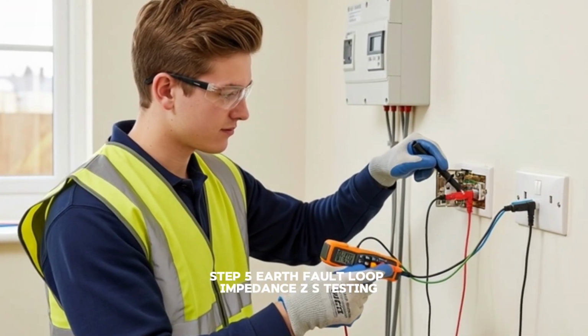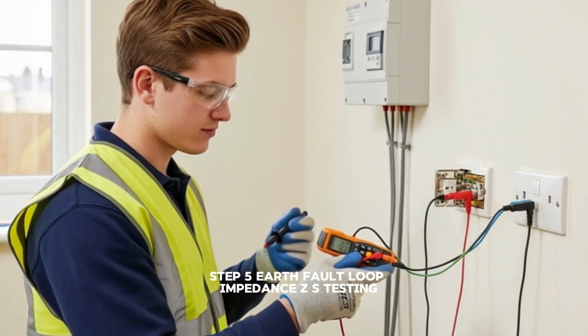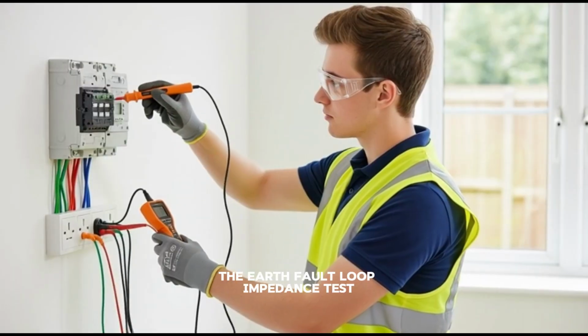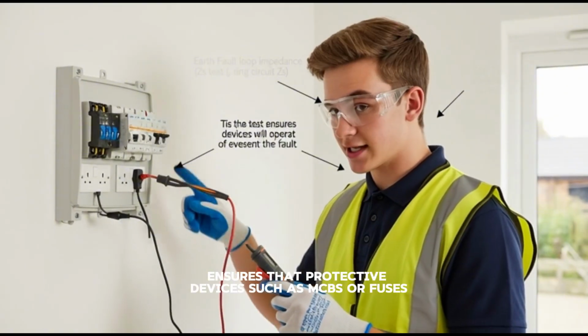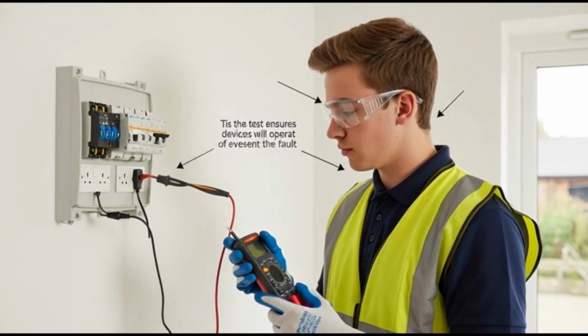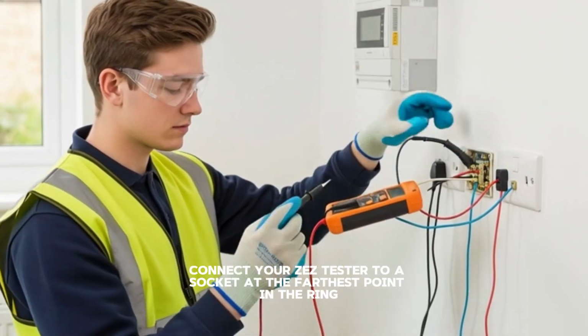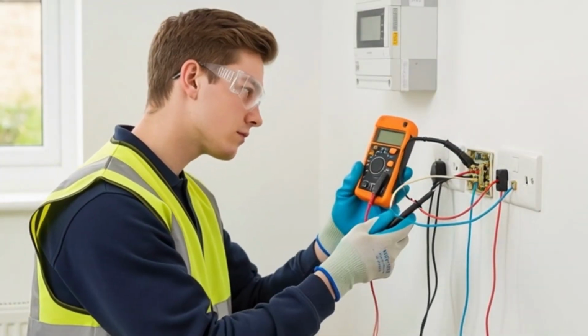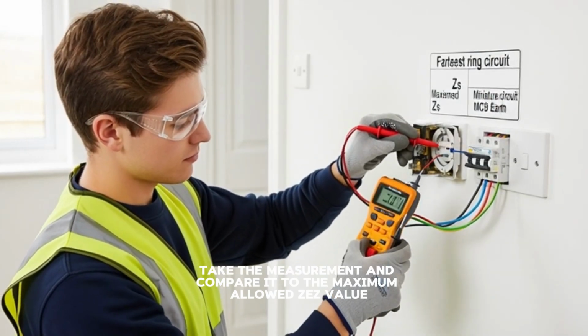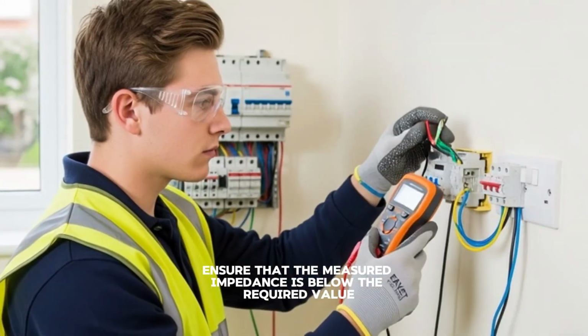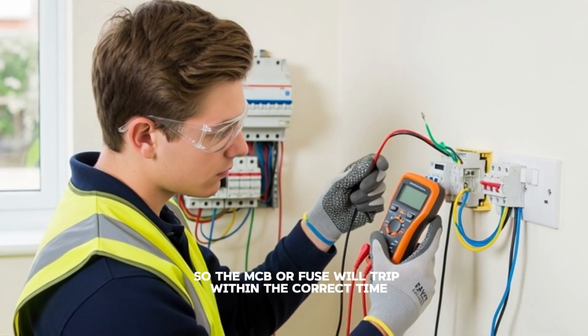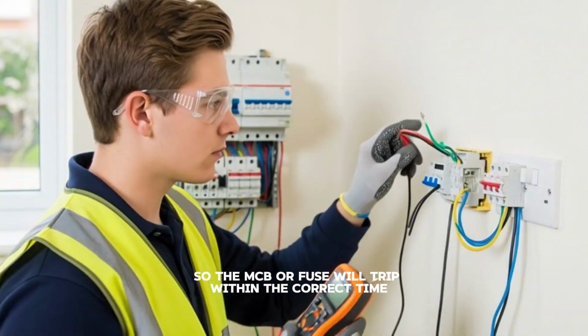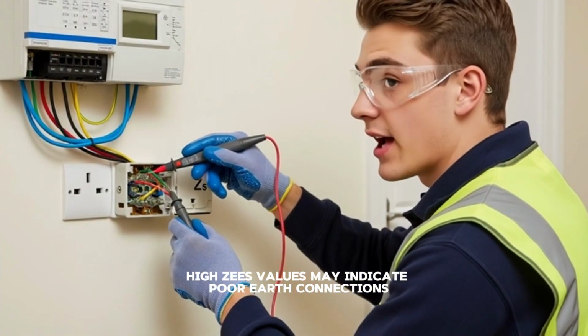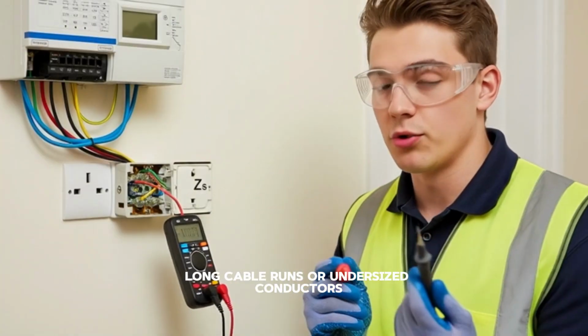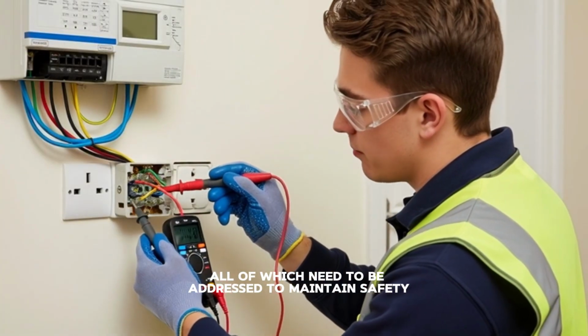Step 5. Earth Fault Loop Impedance (Zs) testing. The Earth Fault Loop Impedance test, often called Zs testing, ensures that protective devices such as MCBs or fuses will operate quickly in the event of a fault. Here's how to perform Zs testing. Connect your Zs tester to a socket at the farthest point in the ring. Take the measurement and compare it to the maximum allowed Zs value for the protective device. Ensure that the measured impedance is below the required value, so the MCB or fuse will trip within the correct time. High Zs values may indicate poor earth connections, long cable runs, or undersized conductors, all of which need to be addressed to maintain safety.